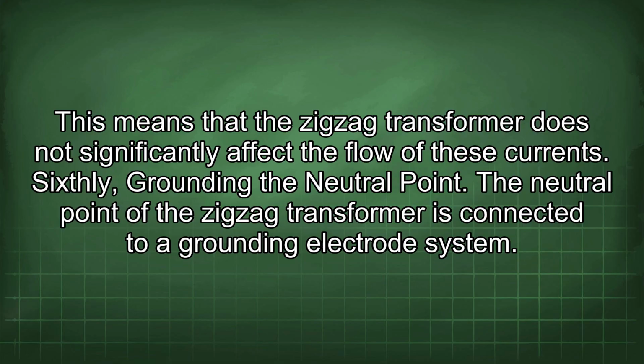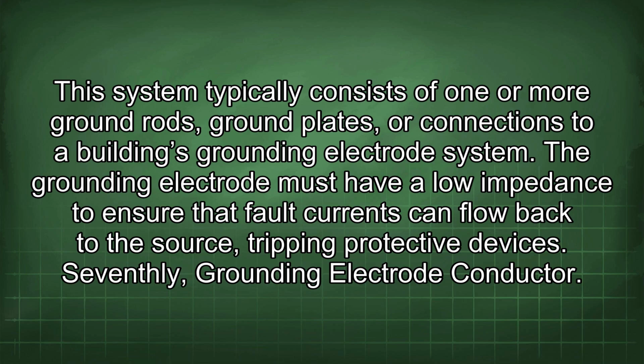Sixthly, grounding the neutral point. The neutral point of the zigzag transformer is connected to a grounding electrode system. This system typically consists of one or more ground rods, ground plates, or connections to a building's grounding electrode system. The grounding electrode must have a low impedance to ensure that fault currents can flow back to the source, tripping protective devices. Seventhly, grounding electrode conductor.